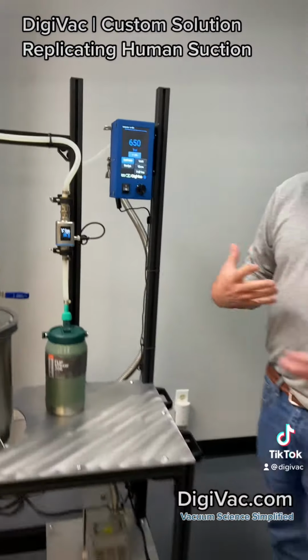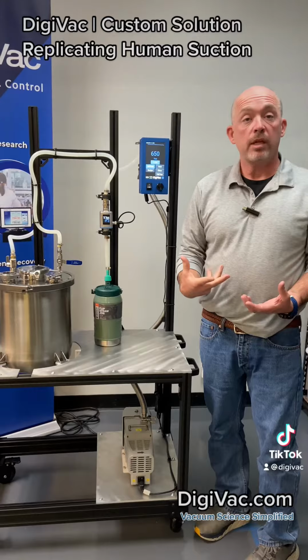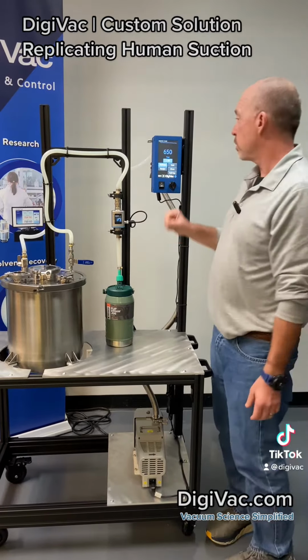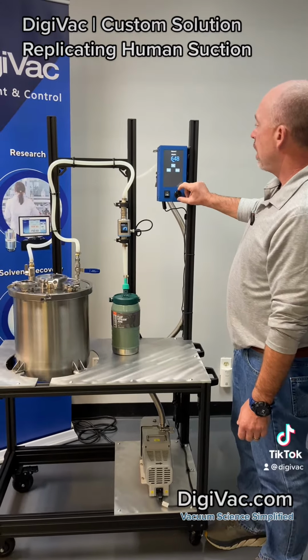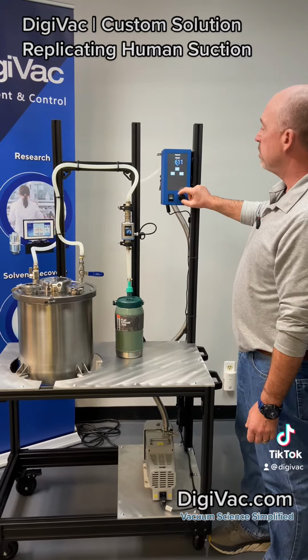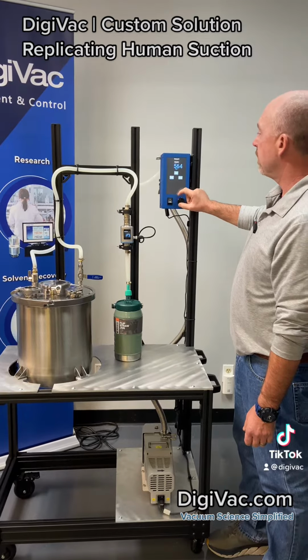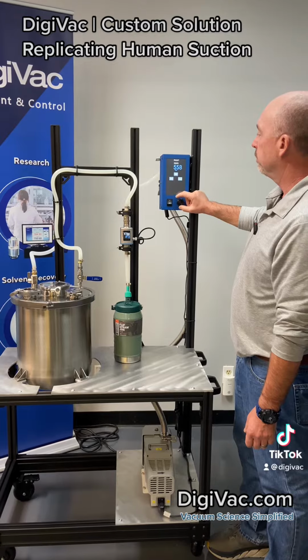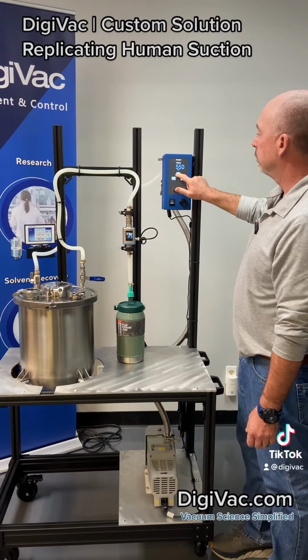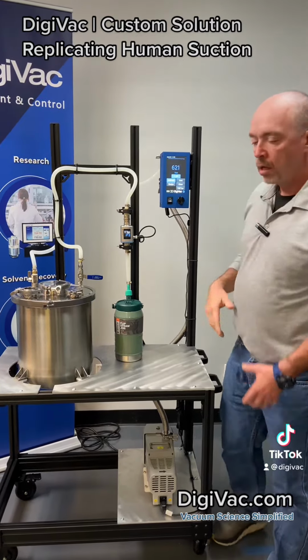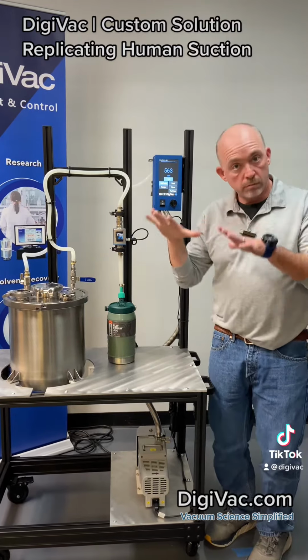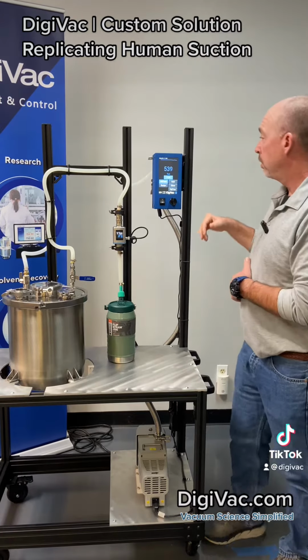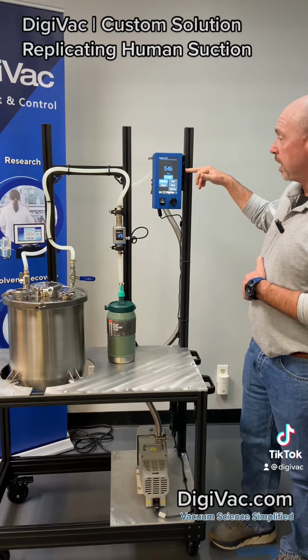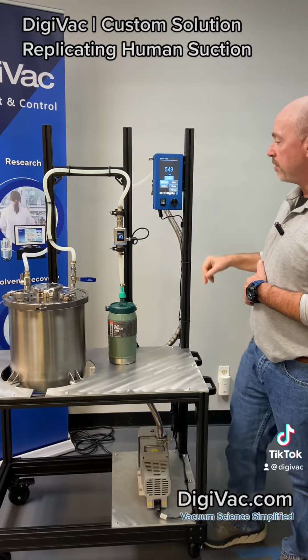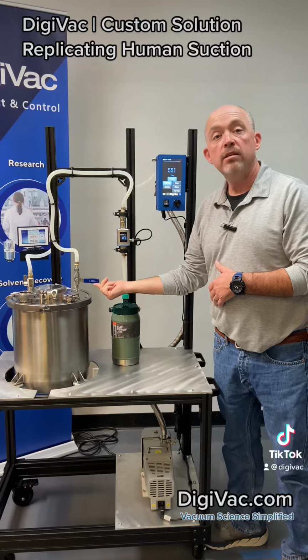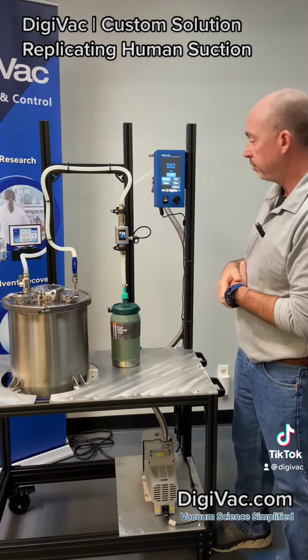Pretty interesting, right? Now, what happens if we actually suck harder? So let's do that. So let's change the vacuum level a little bit lower, say to 600 or 550, let's say. So another 100 torr less. So now the Snap will bring the vacuum level down pretty quickly. Okay. So we'll wait for it to be 550. And now we'll go ahead and see what change that has.